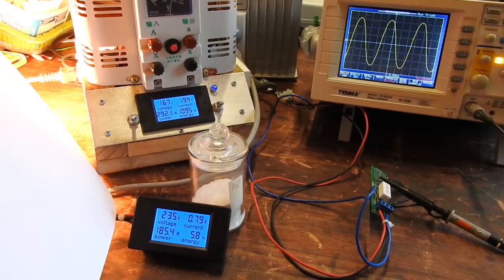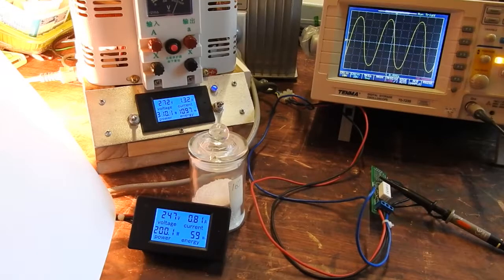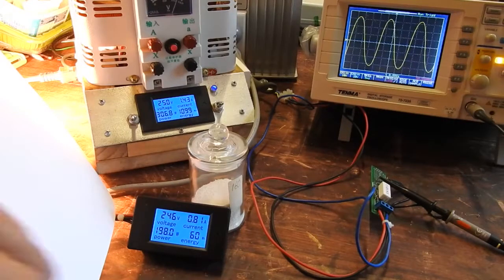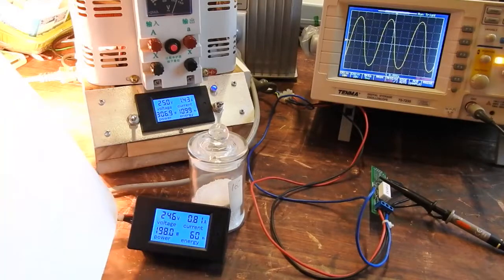Bit of phase shift. The scope's triggering on line frequency, and you saw there's a bit of a shift, which is something ferroresonant transformers do. They shift the phase slightly. 200 volts going in, rounding, but yeah, and that's 286 going in. So that's pretty good. It's not a perfect sine wave, but most things would be fooled by it. But for 250 in, 246 out, at its rated load efficiency, 300 going in, 200 coming out.